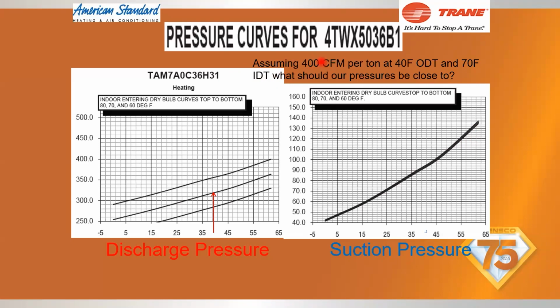We're making sure our indoor unit's set for 400 CFM per ton. We have a 40-degree Fahrenheit outdoor temp and a 70-degree indoor temp. What should our best pressures be close to? Right there. So we're intersecting with that 70-degree line. We're coming up. We want about 320 head pressure on this day. Suction pressure, same thing. Follow it up, connect to the line. We want about a 93 suction pressure on this day.